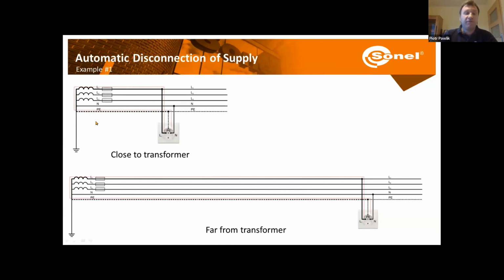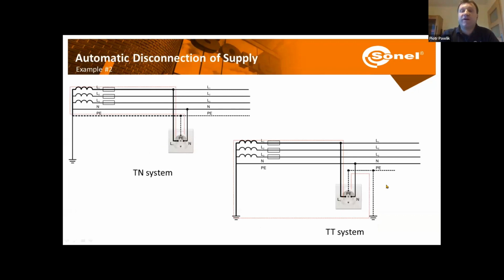Why is that? Well, we are measuring the impedance of this loop. So that's the resistance of the wires, the reactance of the coils in a transformer. But look over here, the wires in our network, in our walls, will be just shorter. Here they are further away. So obviously the resistance of the longer wire is higher than the resistance of a shorter wire. So that's why the closer to the transformer we are, the lower will be the value of measured fault loop impedance. Another example: where will measured fault loop impedance be lower, in case of a TN system or a TT system?